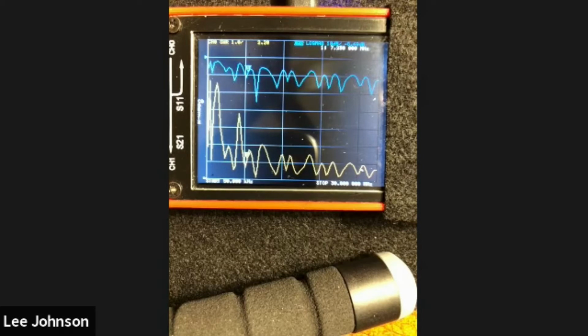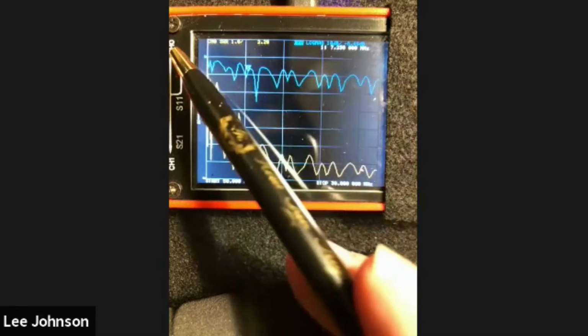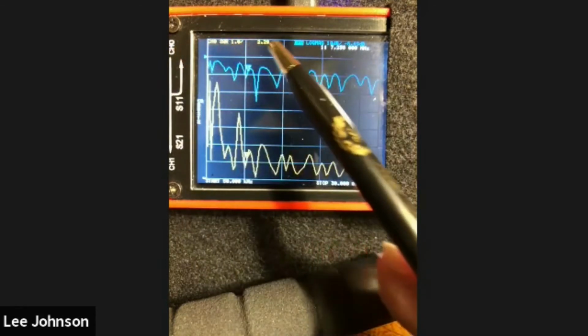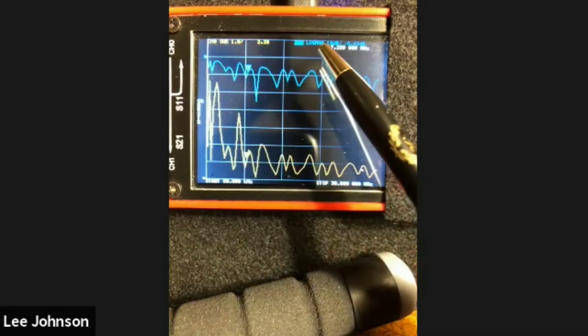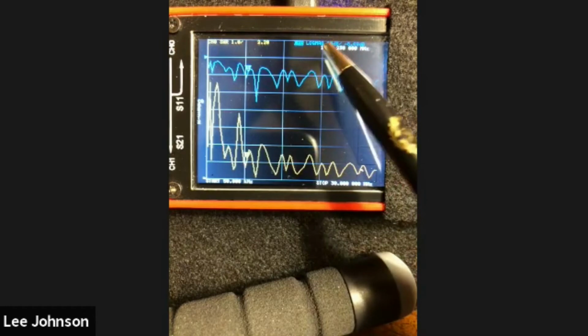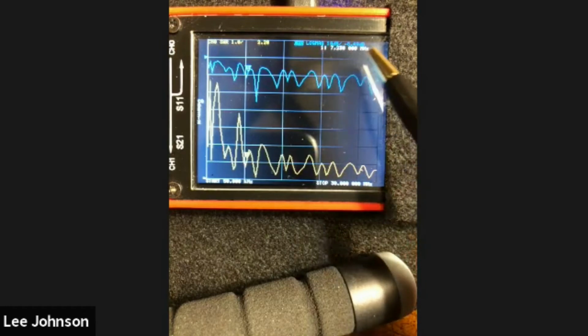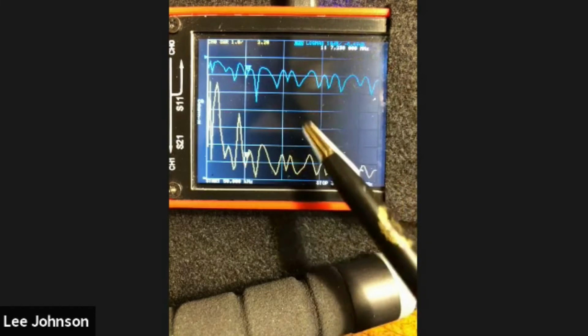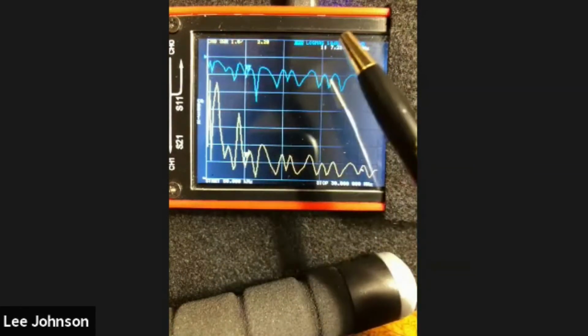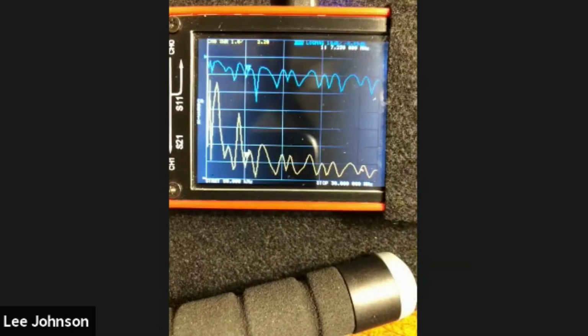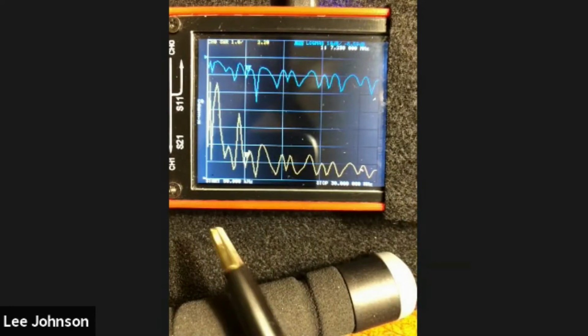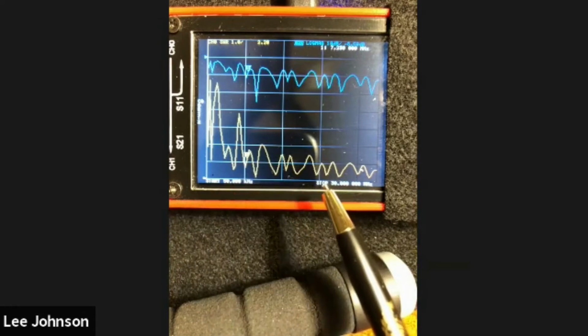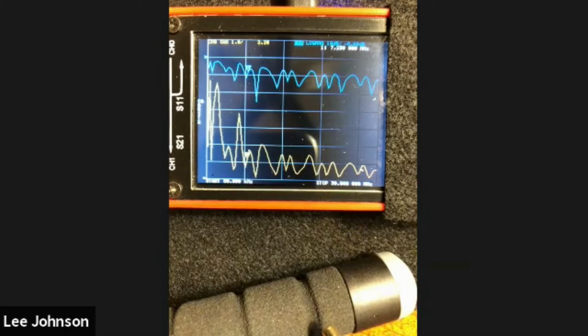Okay. Well, the only point I'm trying to make here is that you have a definition of what the yellow trace is and the value. And here you have a definition of the magenta, I guess it's cyan, trace, and what it means and what the value is. And you can put all 4 of them up and you'll see them written up here in the top left and right portions of the scales. On the lower you'll see the frequency span typically of what you're taking a look at. So that's the way to read the first order, what's going to be on the screen and where do I look to try to find it. Okay.